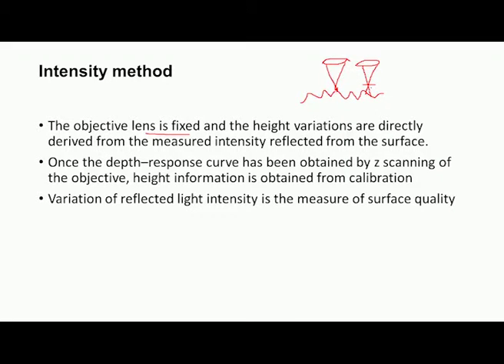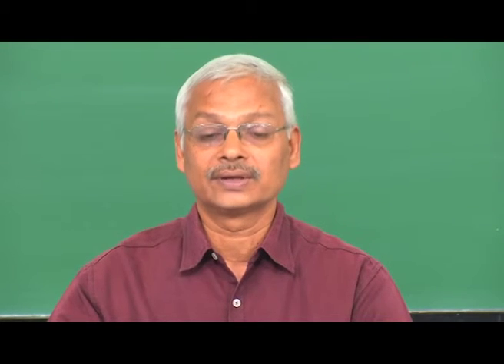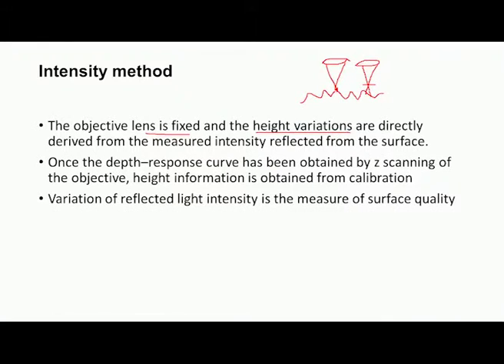So, depending upon the asperities, the reflected light intensity falling on the detector will vary. Those variations in the light intensity give us the height variations on the surface of the workpiece. What we have to do is collect all the measured reflected intensities, and then manipulate those data, and then we can find the roughness parameters.